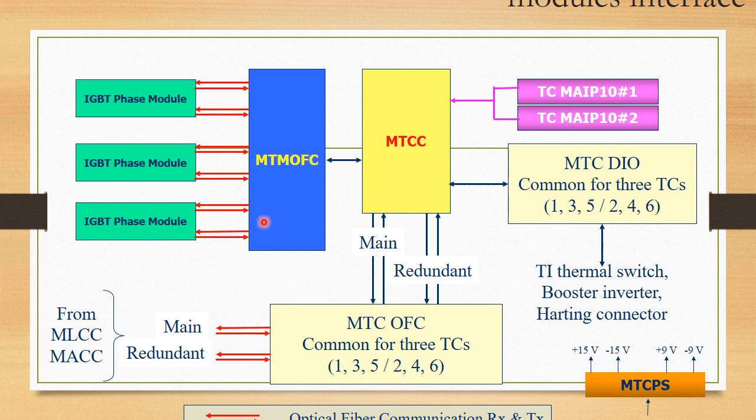These communications are through optical fiber cable. The MTCC card is also fed analog data — voltage, current, temperature, pressure — through different sensors via two analog input cards MAIP10#1 and MAIP10#2. Two digital input/output communication cards are common for one side's three computers. These common cards communicate with the main traction computer cards 135 and 246, feeding digital inputs to the computers and taking digital outputs to the user.